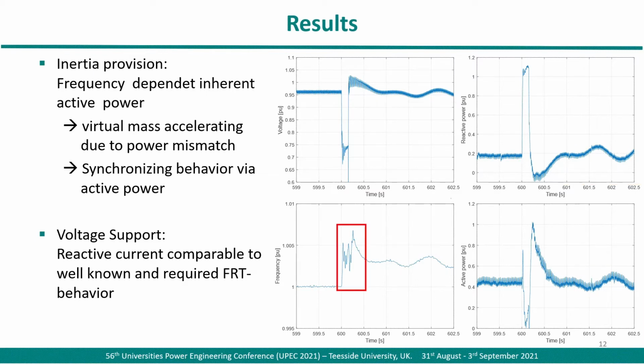The frequency will rise due to the fact that some loads were decoupled, so that there is a power mismatch at the synchronous generator. The well-known reactive power behavior is visible to support the voltage recovery. In the graph for active power, the reduction due to the voltage drop is observable. In other cases, there could be other priorities except reactive power. After fault clearing, the power is rising to synchronize itself with the grid.